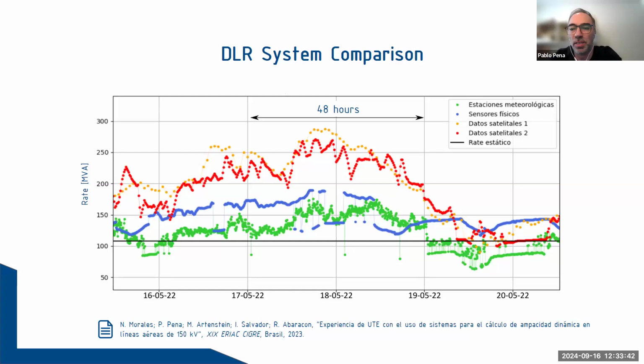And the reality is more challenging, especially for sensorless systems that rely on models to estimate the environmental variables along the line. And in this example, over a 48-hour period, the sensorless system overestimated the line's capacity, and for nearly half a day, they estimated double the actual capacity. Well, for more details on this comparison, you can refer to the paper we presented at CIGRE last year. So the question is what? Why? What failed?